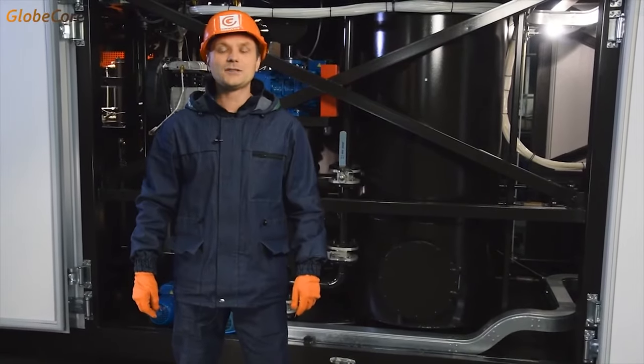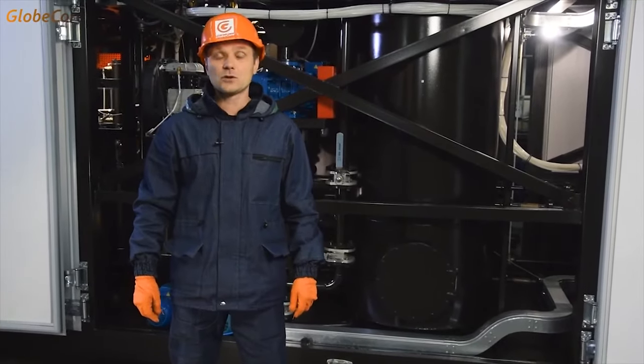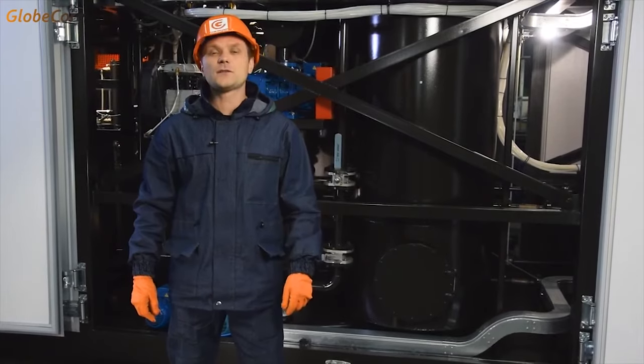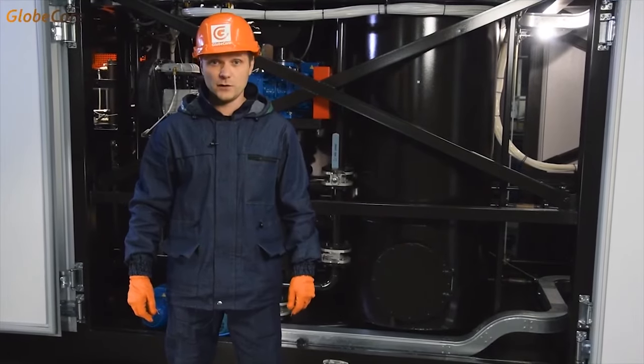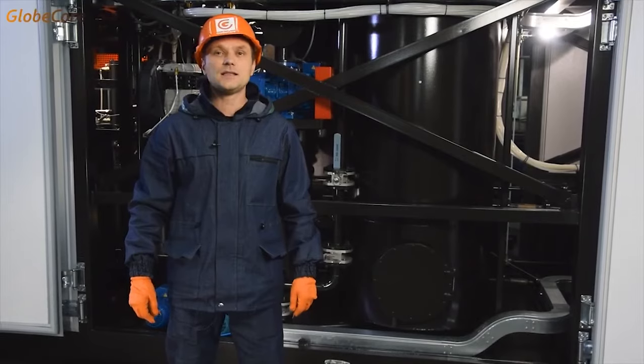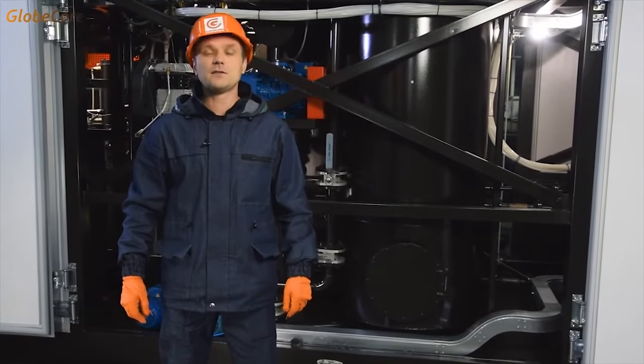One more thing that I find particularly great is that the regeneration technology is not limited to transformer oil only. The machine can be efficiently used with other petrochemical products, such as diesel fuel or heavy heating oil, hydraulic and vacuum oils, etc. If you are faced with the task of petroleum product recycling or purification, share your task with us, and we will gladly accept the challenge and apply our accumulated experience to meet it.